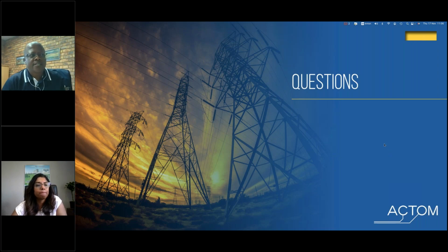Okay, the site is located in Cape Town, and there are extremities in temperature. The farm in question is called CPV1, it's a solar farm where the panels do solar tracking. During the day it gets extremely hot, above 30 degrees, but in the evenings the temperatures drop to just below zero, say -1, -2. With those extremities in temperature change, unlike other areas where you get just a few degrees change between day and night, the transformer was subjected to severe expansion and contraction. During the day they're fully loaded because it's a solar farm, but in the evening they're just energized and kept running.